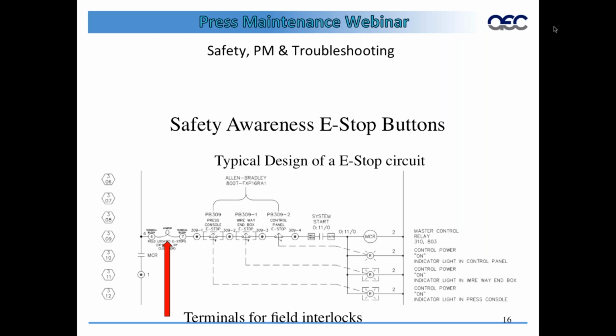Typically, for some systems, a supplier will produce designs within the electrical systems so that you can strategically place emergency stop buttons around your system, regardless of how big it is or where people are working, wherever you think someone should be able to quickly hit an e-stop. This drawing shows what's typically done if the system is designed well: a jumper is left so you can add onto the series circuit wherever you want around your plant equipment. If it's a good design system, you'll see that when you pull your electrical drawings.